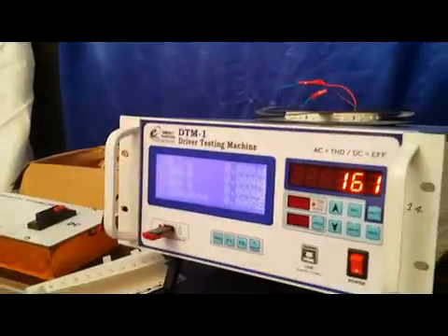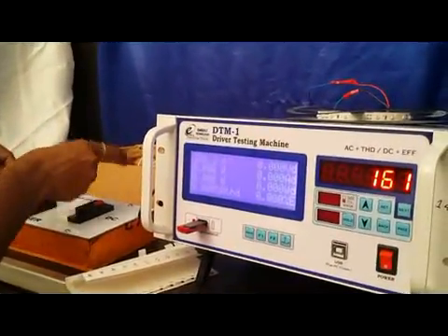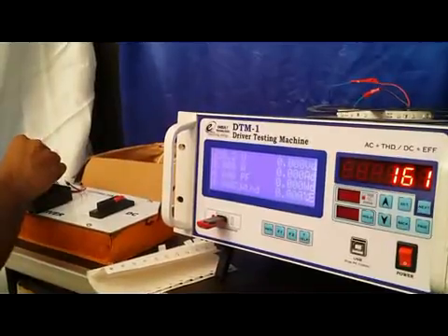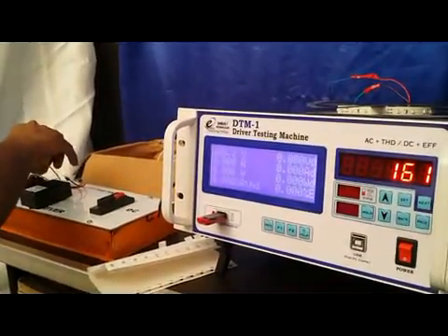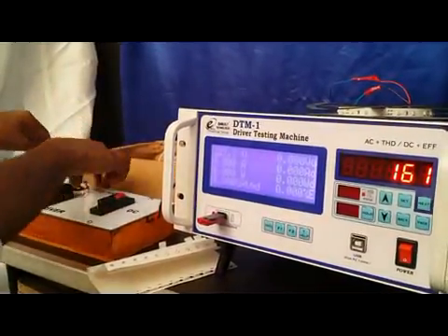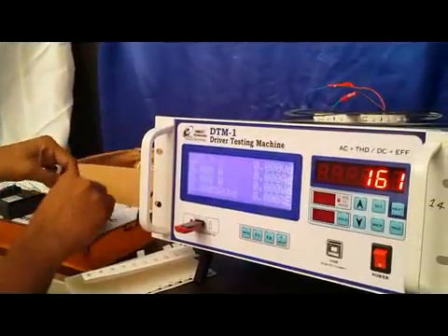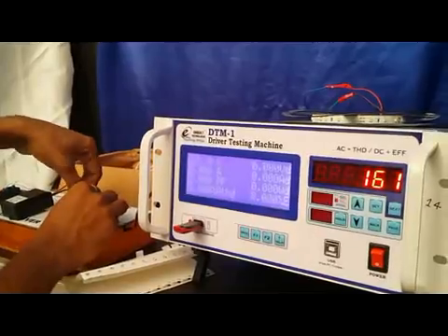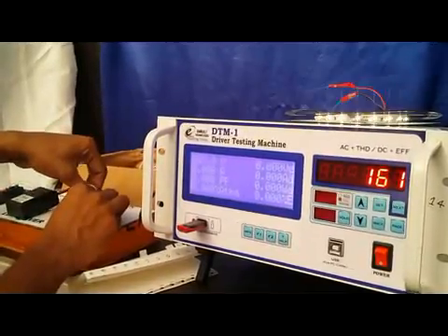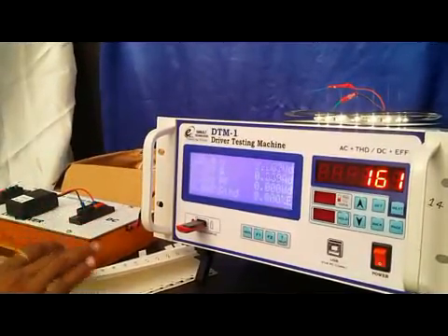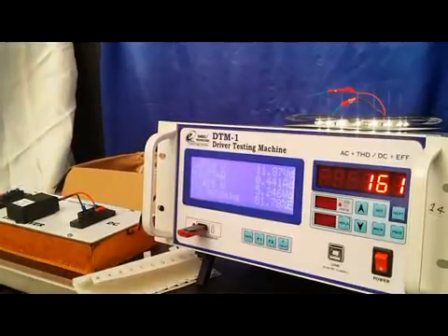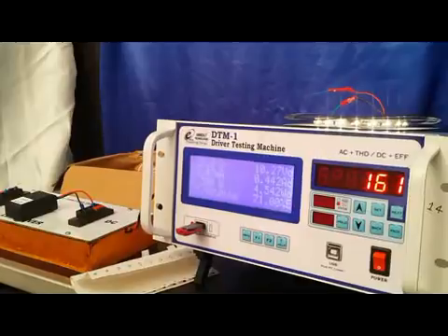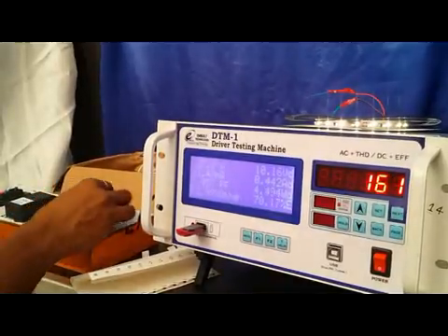Now he is connecting a new driver. So he connects the AC part, then he connects the DC part. So now it is showing fail. So apparently one parameter is showing fail. I can see that in the middle of the first line, it is showing fail, THD %80. So the current THD value is more than the pass limit.